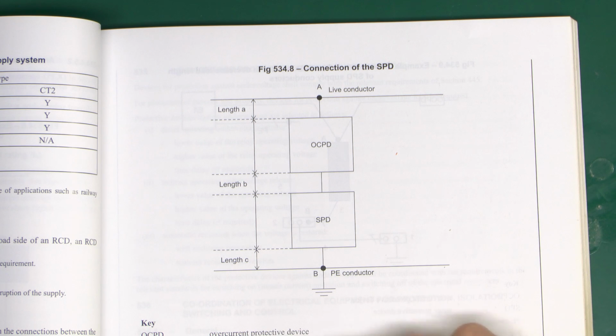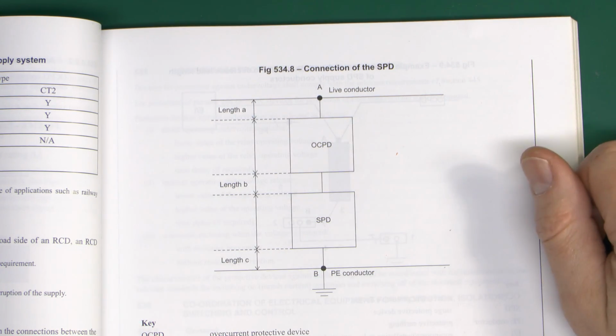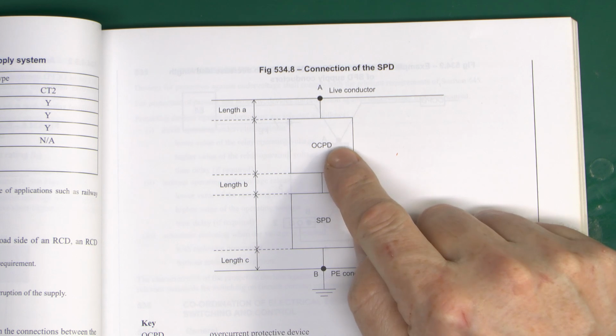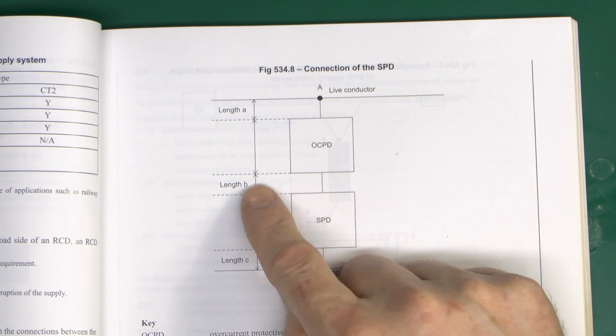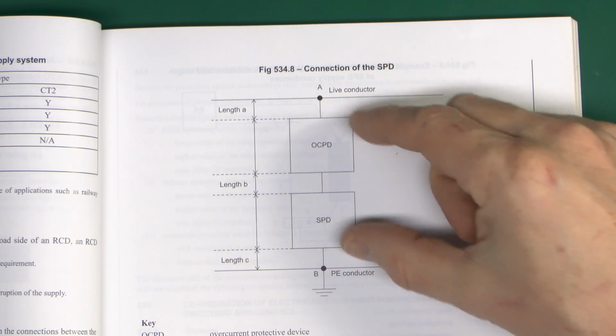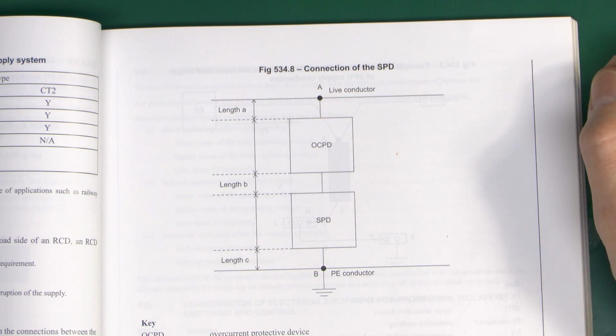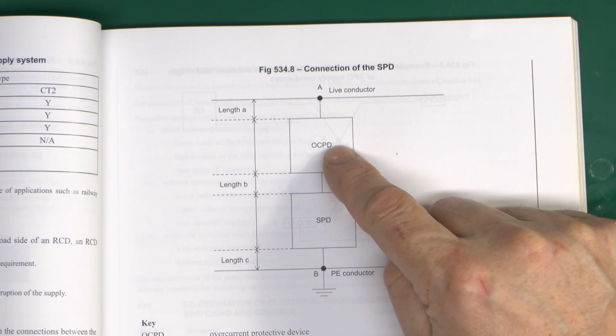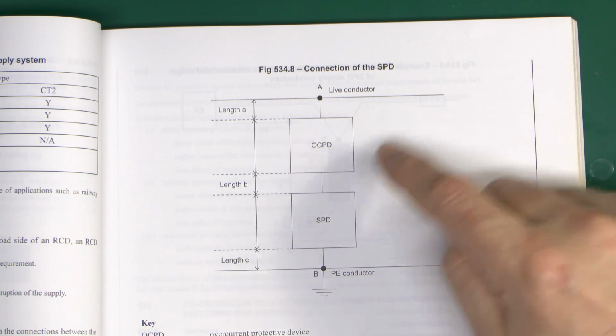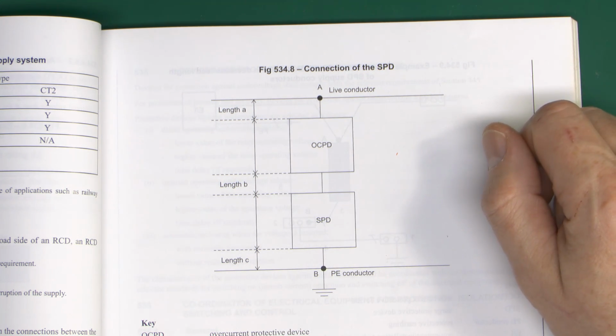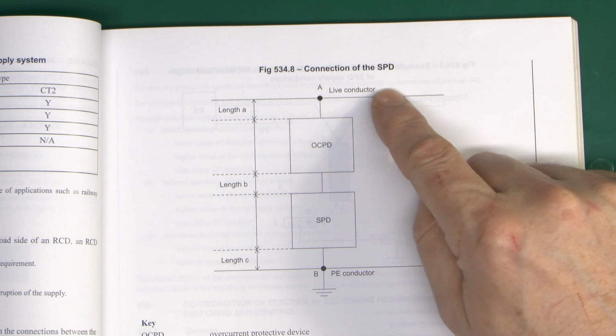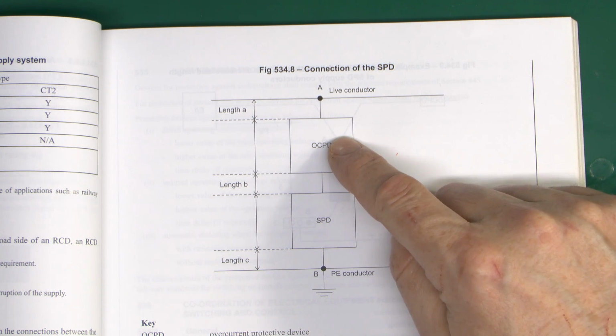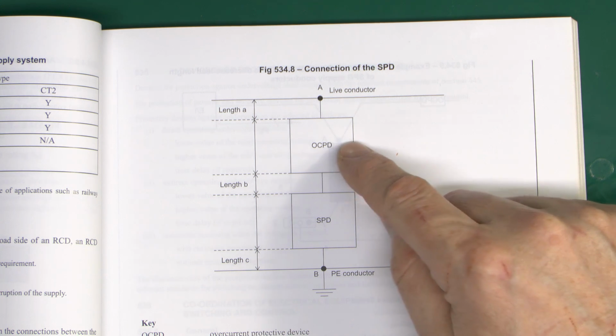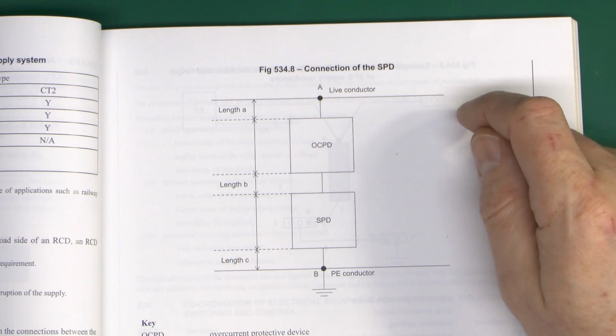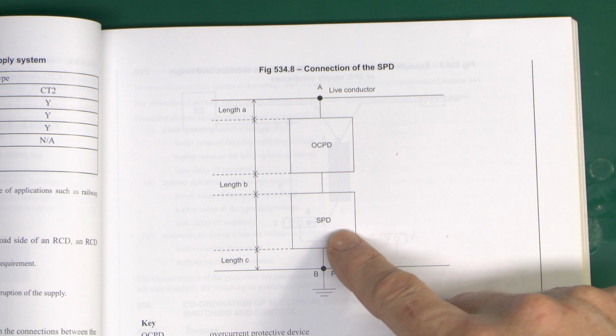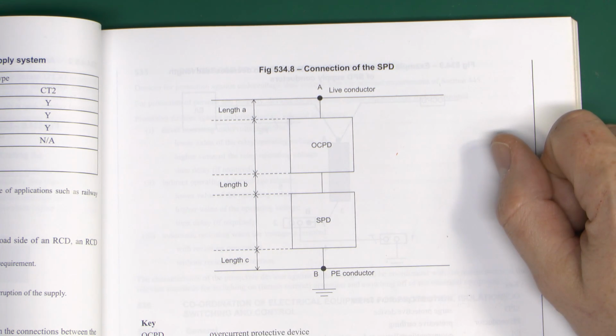Now this is where the lengths thing comes in, and we can see three lengths here, A, B and C. Obviously if this is inside the actual whole assembly, then of course length B won't exist, it's just going to be length A and C because you won't see what's inside the device. But if you've got a separate, say, circuit breaker outside, and that just loops over to the surge protective device, then of course length B will exist as well. So A is between the live conductor and the overcurrent protective device. Length B is between the overcurrent protective device, say circuit breaker, and the surge protective device, and length C is the bit between the surge protective device and the earth conductor.